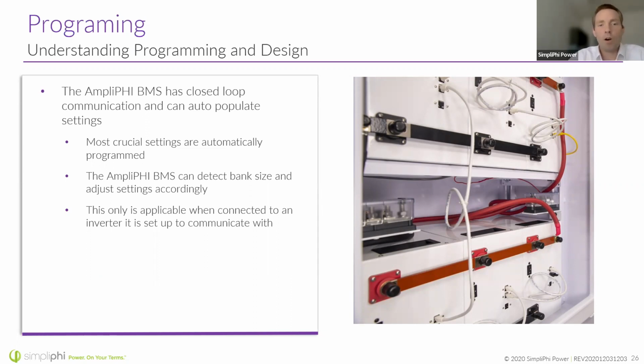The BMS can automatically communicate the size of the bank, because it knows when the BMS unit is connected to other units—it knows how many units are in parallel. It knows the state of health. It knows the temperature across those 16 stacks of cells. So a lot of information is sent through these closed loop communications.